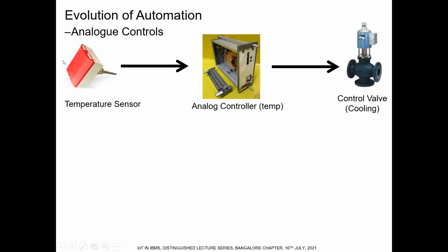And then we had analog controls, a slightly more sophisticated level of automation. We had a single temperature sensor. Whenever you had a sensor, it had to be connected to a controller, and then it was driving a valve. You can see here a single sensor means a single controller. A single controller could drive only one actuated device. It could not drive multiple actuated devices, but it could actuate one device: one parameter, one controller, one control parameter, one control device.